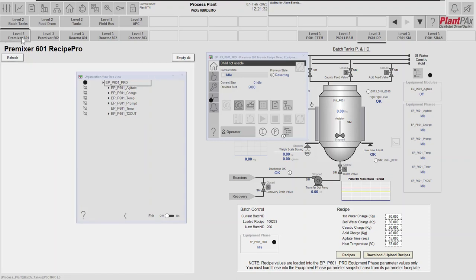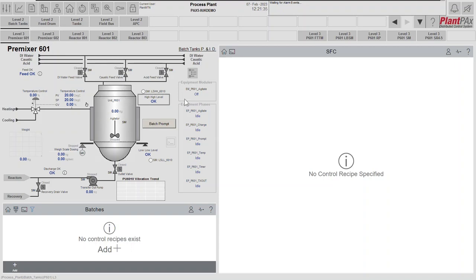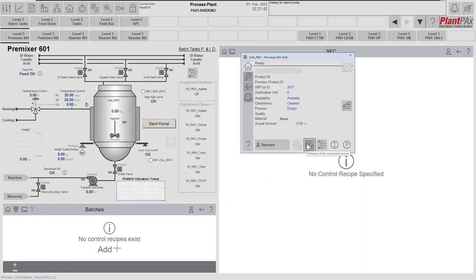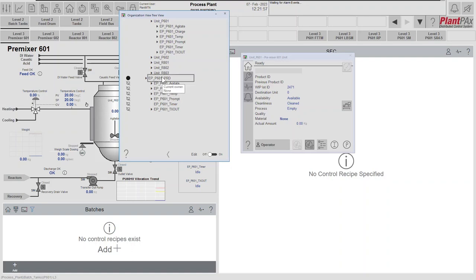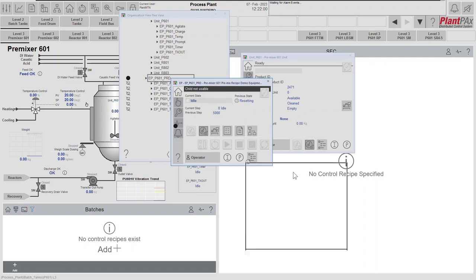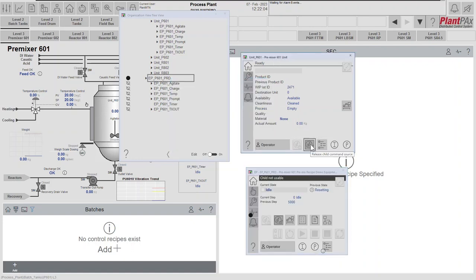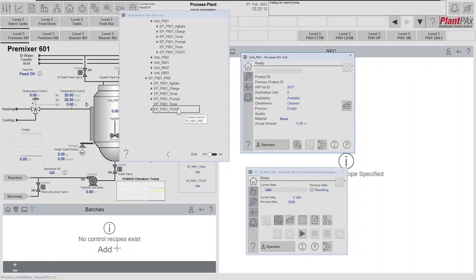Going back into premixer 601 and opening up the unit faceplate, we can tell the unit to release its children. Before doing that, I'll bring up the tree view so we can see what happens. We can see that the premixer 601 unit is owning all these phases, and the other equipment phase is trying to own them but currently unable to acquire them. When we go to the unit and release its children, as soon as the children become available, the other equipment phase that was trying to acquire them will acquire them - and now they are owned by it. That's the end of our demonstration of some of the key features of Organization, Ownership and Arbitration.